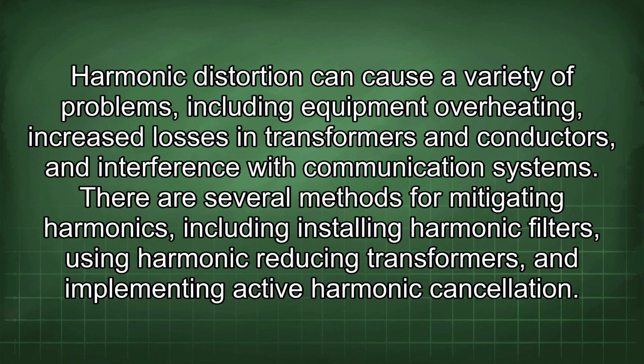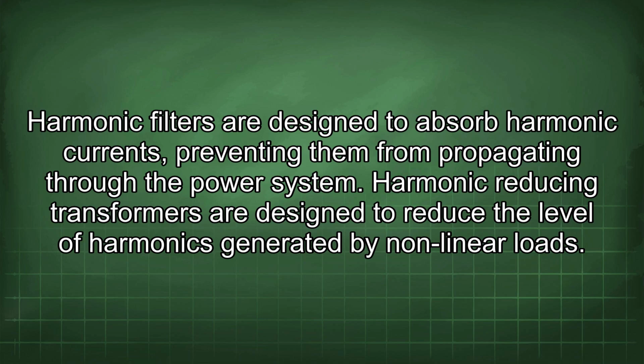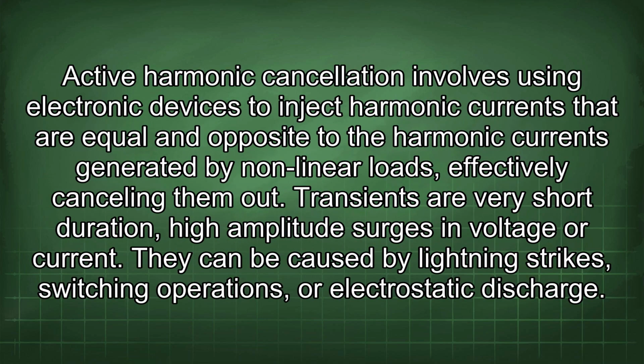There are several methods for mitigating harmonics, including installing harmonic filters, using harmonic reducing transformers, and implementing active harmonic cancellation. Harmonic filters are designed to absorb harmonic currents, preventing them from propagating through the power system. Harmonic reducing transformers are designed to reduce the level of harmonics generated by nonlinear loads. Active harmonic cancellation involves using electronic devices to inject harmonic currents that are equal and opposite to the harmonic currents generated by nonlinear loads, effectively cancelling them out.